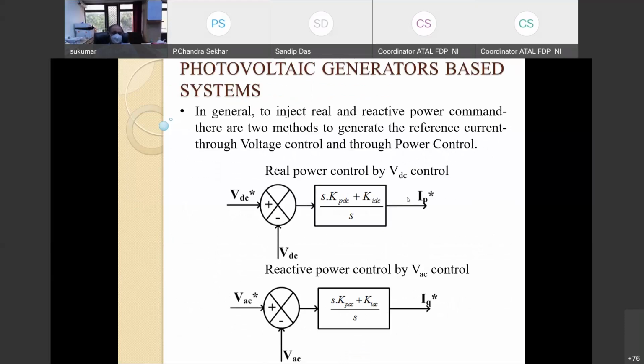To achieve that, the DC voltage control is imbibed, where the DC voltage control provides the real part of the current, which can be your loss component or your command component. Generally, if it is added with a command, then we add a summer here and put in a command, so that the loss is provided by the VDC reference minus VDC control, and a separate command is provided to give the desired amount of current.